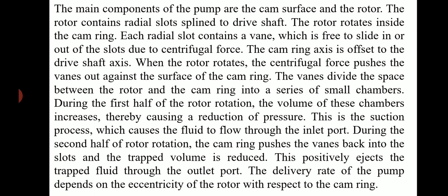The rotor contains radial slots splined to the drive shaft. The rotor rotates inside the cam ring. Each radial slot contains a vane which is free to slide in or out of the slots due to centrifugal force. The cam ring axis is offset to the drive shaft axis.